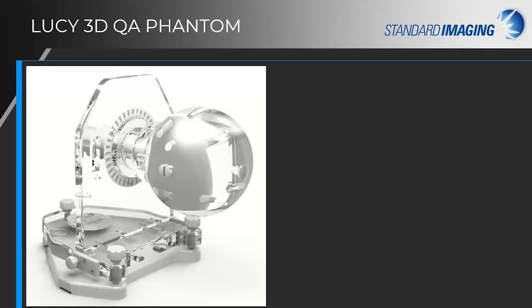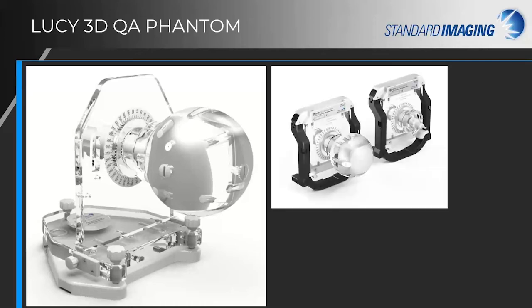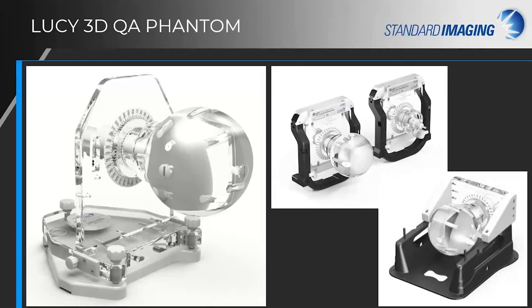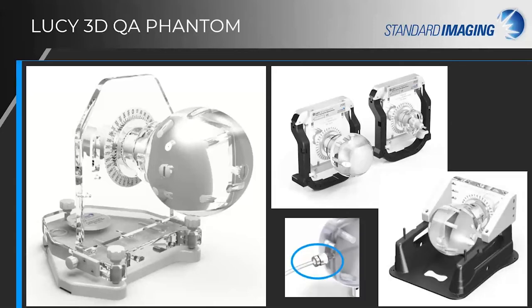So to summarize about the Lucy Phantom, whether you're using it on its standard precision leveling base locked to the couch bar, or you lock the Phantom or pointer into the isocentric coordinate system using an interface, or you want to ensure the centroid of your detector's collecting volume is at isocenter, you can be confident that you are performing excellent SRS end-to-end QA and truly to the best precision and accuracy using the Lucy Phantom.